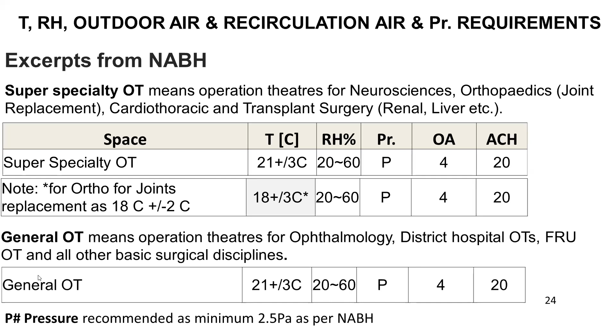Now, this 2.5 pascals is something which we need to think about. It's a pressure that you can hardly measure on a gauge. So why it is written 2.5 is a matter of conjecture. But if you were to design an operation theater, the minimum that is recommended, for example, in CDC is 7.5, which is a little more reasonable. So if you do 7.5, you can at least see it on the gauge properly, and you could be assured that you can also pass the NABH audit.